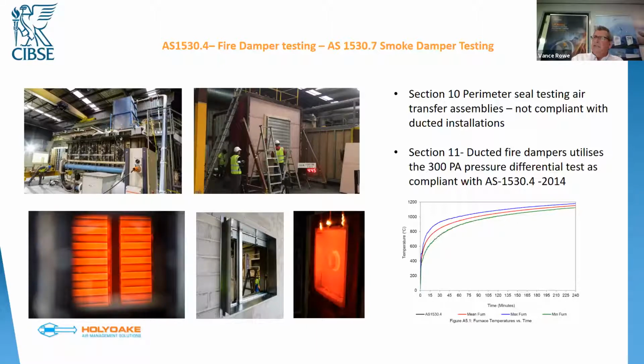Just want to push again the difference between Section 10 and Section 11. Now, there's a lot of claims made by manufacturers out in the marketplace that they're compliant with AS 1530.4. We need to be very clear about what part of AS 1530.4 we're compliant with. All right. Section 11 is for ducted assemblies. So if we've got duct connected to one side or both sides of the fire damper, it must be tested under Section 11 because Section 11 utilises the 300 Pascal pressure differential test and that proves the integrity of the fire damper. Section 10 is a perimeter seal test. So it's only testing pretty much the outside seal of the fire damper against the fire barrier.